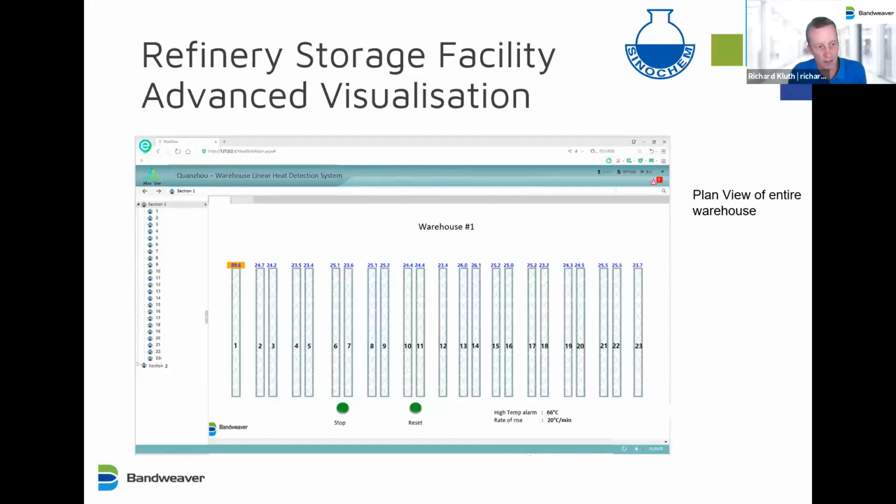In terms of the accuracy, it depends a little bit on the nature of the break, but generally 1 to 3 meters of information you may lose around the break, depending on what the reflection is like at the end of the break. So sort of minimal loss, 1 to 3 meters.